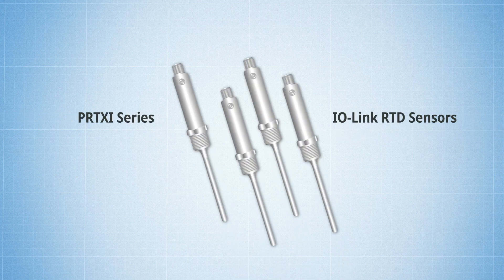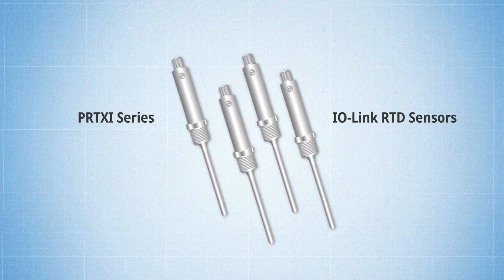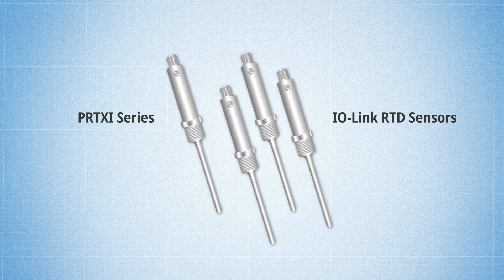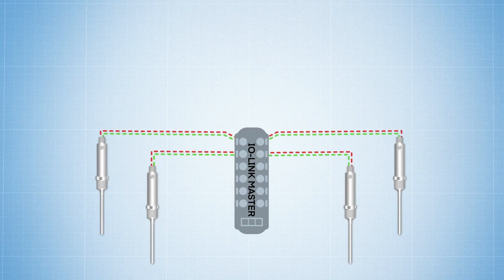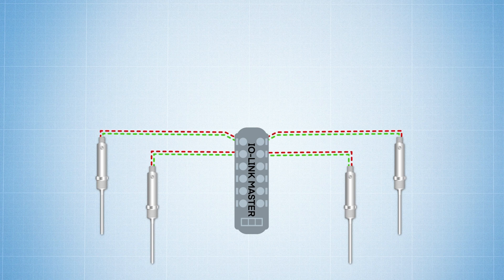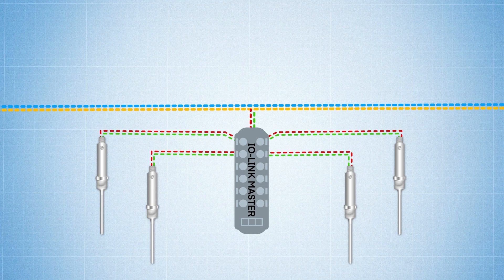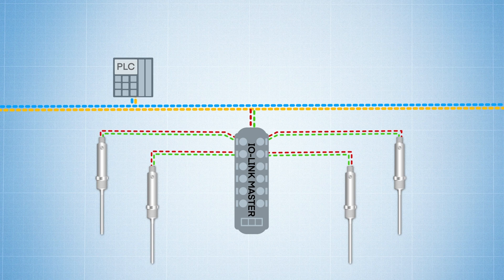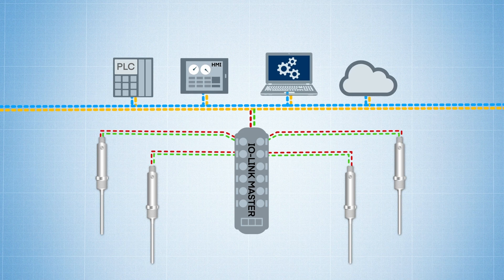Here's how it works. Field devices like these Omega PRT-XI IO-Link RTD sensors transmit and receive a digital signal to and from the IO-Link master. The IO-Link master transmits that sensor data over a network, field bus, or backplane bus to PLCs, HMIs, or up into the cloud.